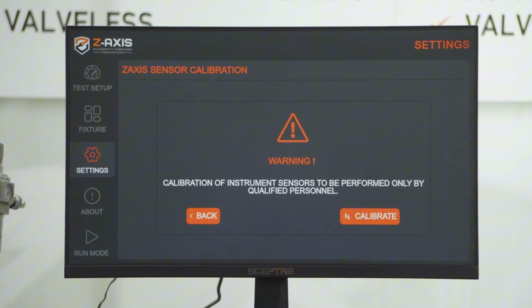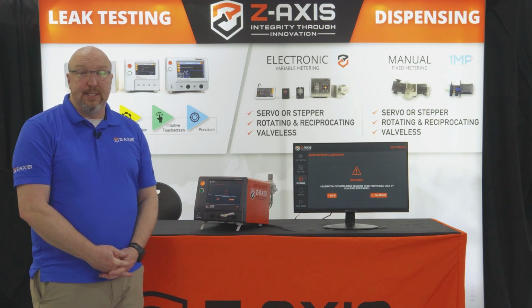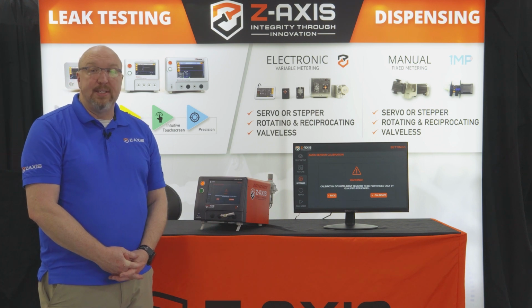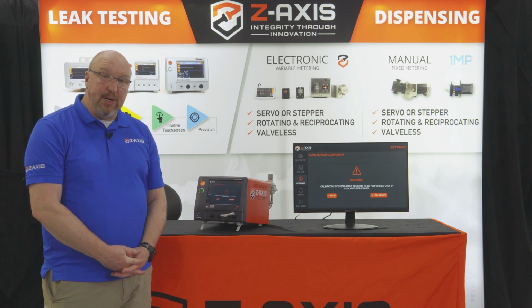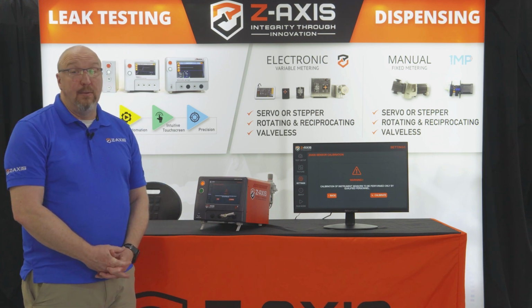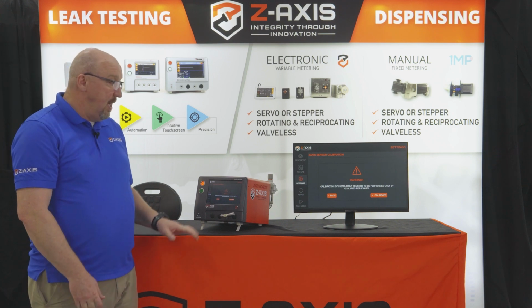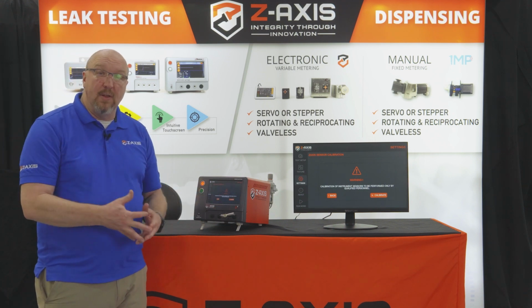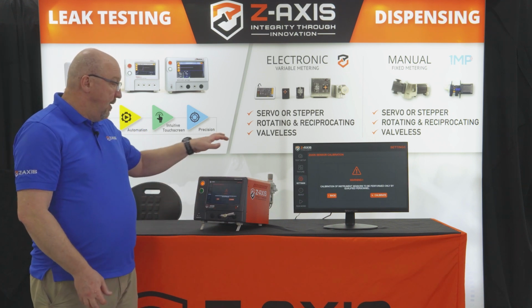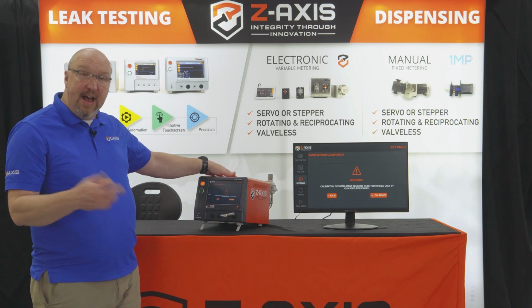Then we have the calibration screen. When this button is pressed, a big warning comes up on the screen and says, don't go in here if you don't know what you're doing. The calibration is really what runs the entire test. If the calibration gets modified, that could affect the results of the test. This is where we calibrate the full scale of all the sensors so that the processor can understand what value it's seeing.